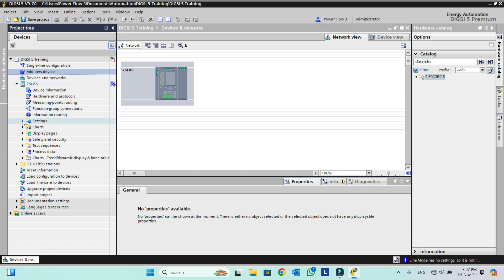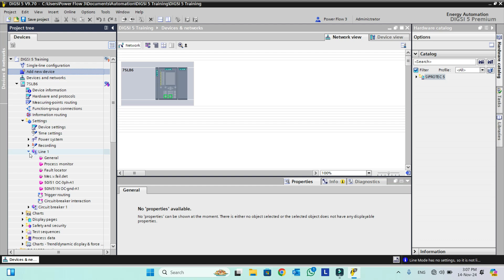This is the 7SL86 relay — the line differential relay. The line could be from a single bus bar or from a one-and-a-half breaker scheme. The Basic version is now added and its hardware is showing because I clicked Open Hardware and Protocol after device creation. In the Settings, under Line 1, General, Process Monitor, only overcurrent (50/51) and VT fail settings are available — no other function blocks or function groups are available because we added only the Basic template. So this is of limited use; we have to add function groups and function blocks manually.